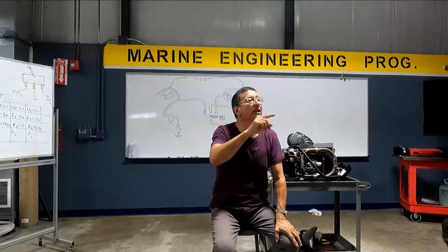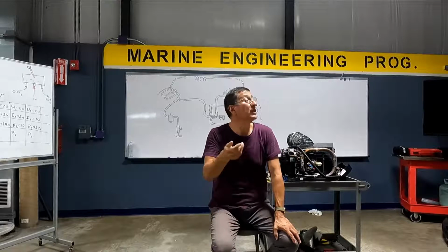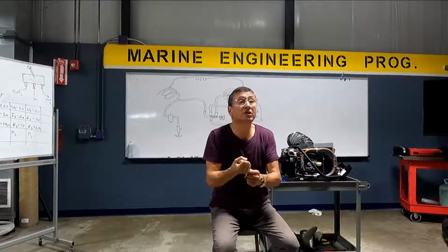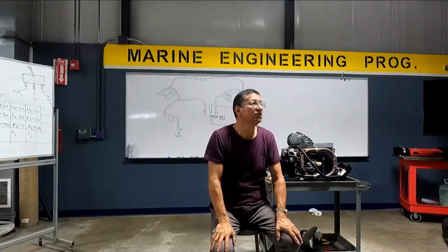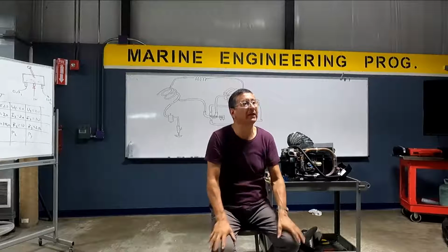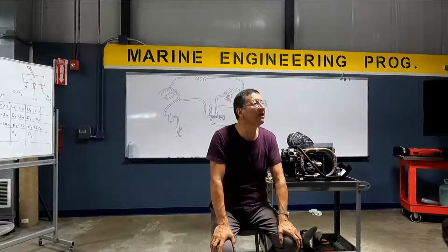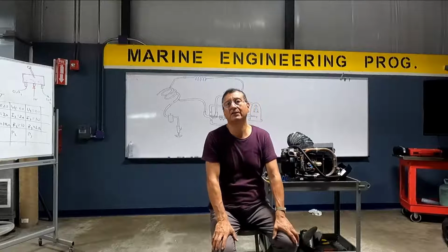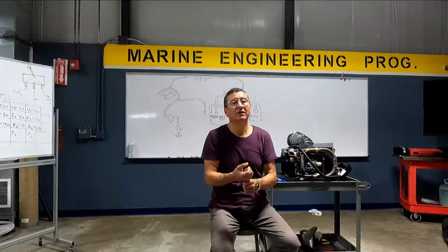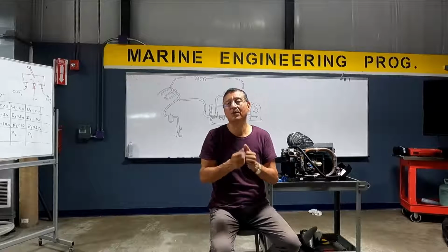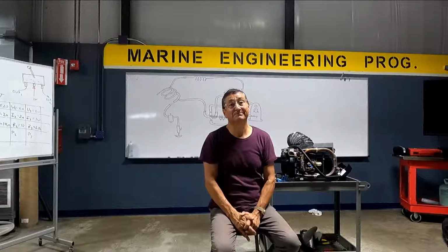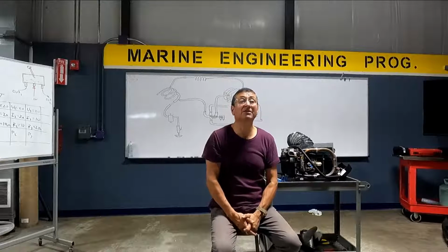Probably that coil is clogged, or the raw water pump is not working, it's broken, or the valve is closed. Some technician during the service closed the valve and never opened it again. That's very, very common for entry-level technicians. And of course, if the raw water pump is running without water, bingo, finito. That raw water pump is expensive.